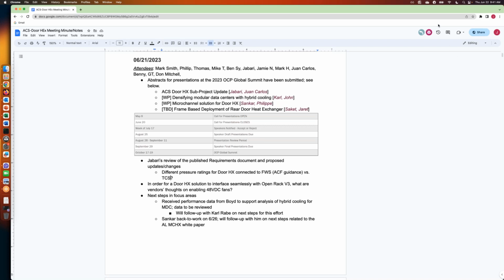John, one question here. We are speaking about two loops. Different loops are pretty much different. I don't know if the cold plate community defined the maximal pressure of the secondary loop. I don't know, but for sure it will not be 10 bars or something like that. Because if you have to couple the quick couplings, the blind mates, the force to again, the pressure will increase, and in some cases you will not have enough force in your hands to put the server inside the system. So from my point of view, it doesn't make sense to have more than 1 bar in the system if you are in the secondary loop. I mean 1 bar relative to ambient, because of some issues, but to have more will bring only problems.